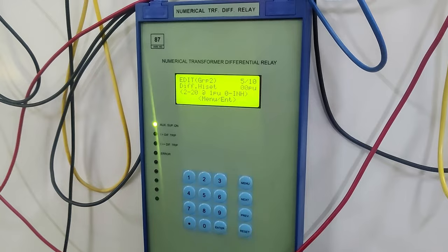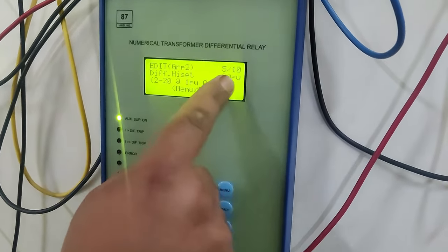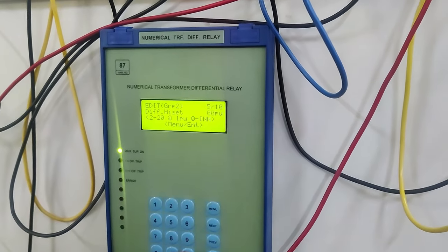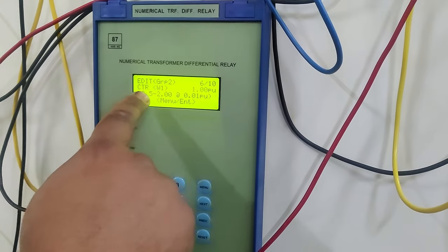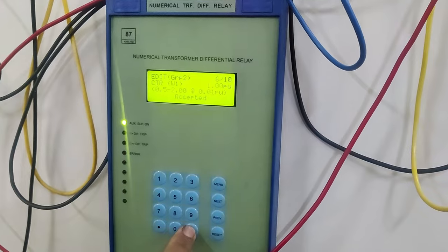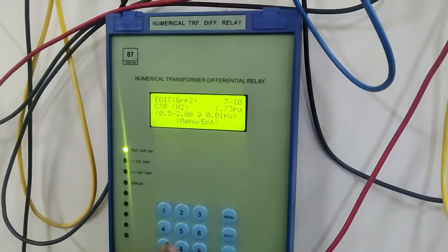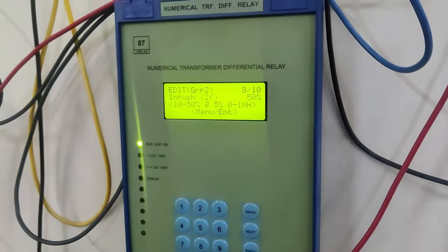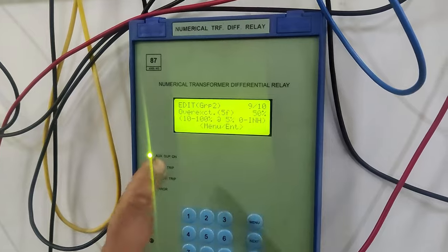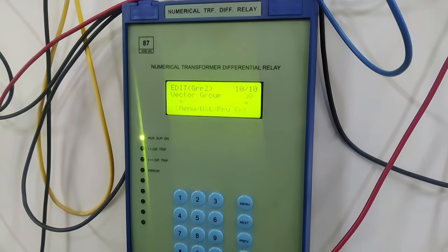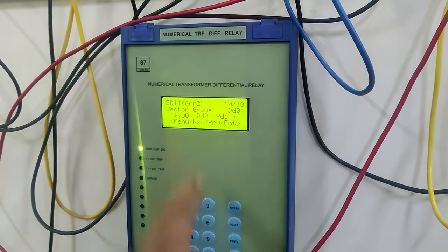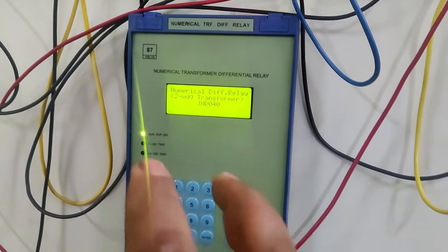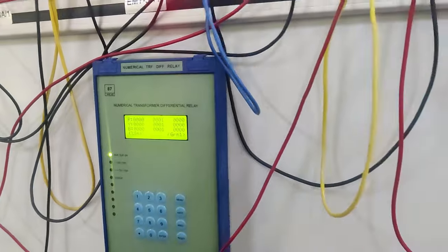We have the differential Hi-set set to 0 per unit. In group 2 we actually have 10 parameters which we can change according to our own choice. The CT ratio W1 is 1 per unit, kept as such. The CTR W2 is 1.732 — let's change this to 1.5 per unit. The inrush is 50%, kept as such. The over-excitation is 50%, kept as such. We have the vector group — choose the DD0 vector group. So we have inserted all the parameters, and I have chosen the pickup value of 0.20 per unit.